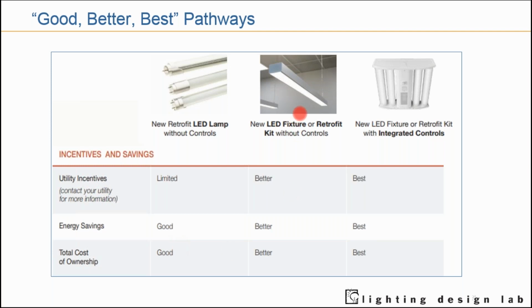Kits or fixtures, new fixtures without controls, will definitely perform better for your savings, and you'll get a little bit more incentivized dollars from a utility. But the traditionally better solution - your fixture or kit with integrated controls, your Luminaire level lighting controls - will give you that $50 to $70 prescriptive incentive. Just because it has motion and daylight sensors built in, your savings will be maximized. Over the life of a new fixture or kit, it will provide you the best savings overall.